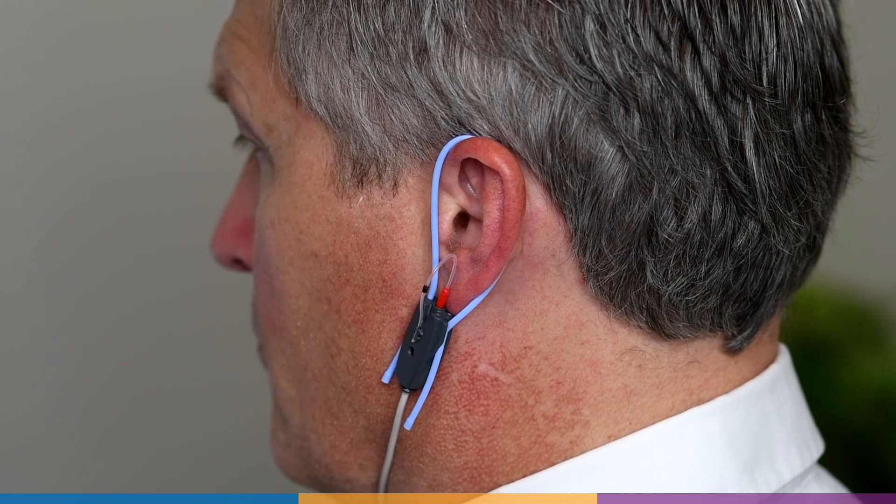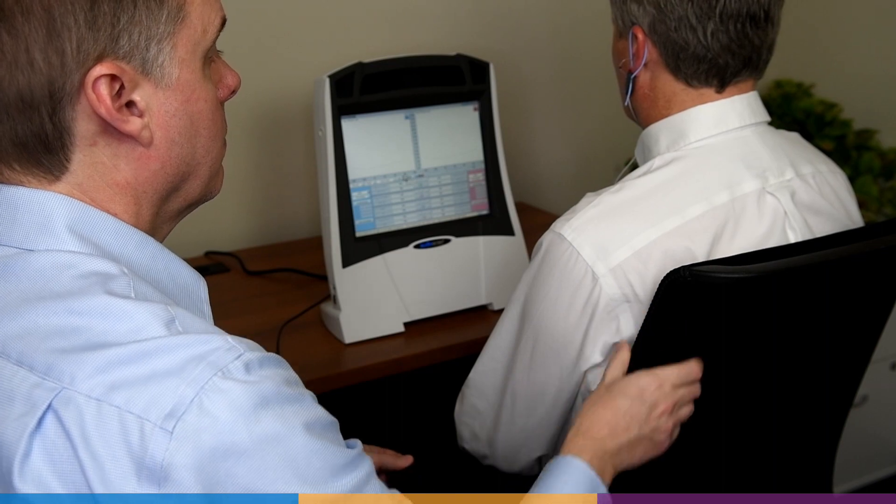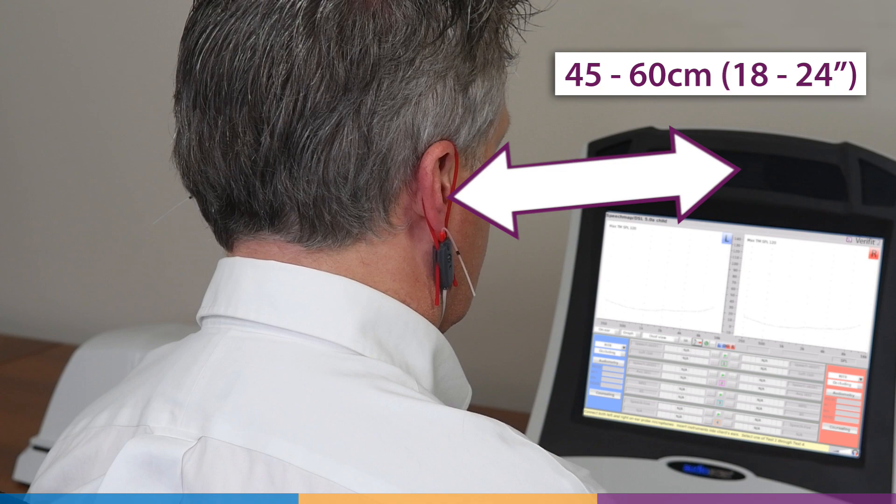When ready for probe tube placement, ensure the client is positioned directly in front of and facing the real ear measurement sound field speaker at a distance of 45 to 60 cm or 18 to 24 inches.